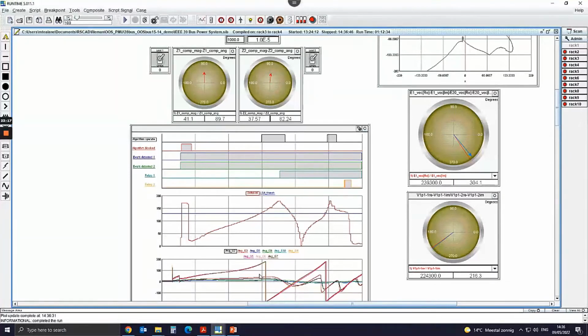Afterwards, when the generator angles start increasing, shown at the bottom here, the algorithm issues an operate command when the angle values go over the threshold value, or the delta value that is computed goes over the threshold value. The protection relays here in the bottom graph show an operate command as well.